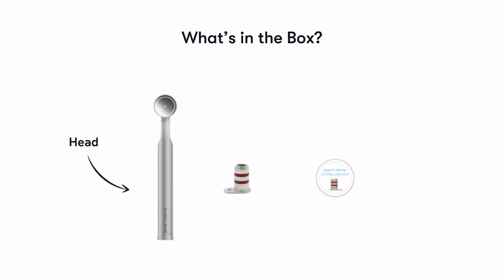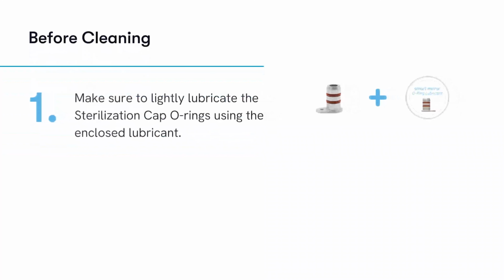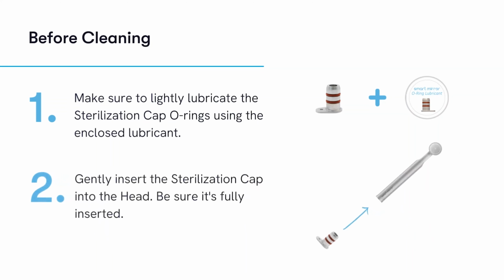Included with your head is a sterilization cap and lubricant. Before cleaning, make sure to lightly lubricate the sterilization cap O-rings using the enclosed lubricant. Then gently insert the sterilization cap into the head. Be sure that it's fully inserted.